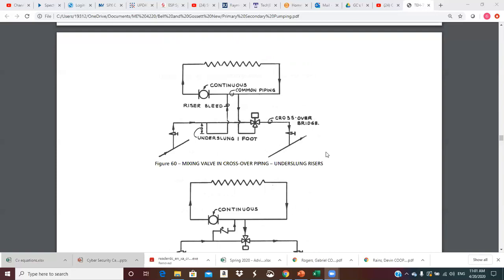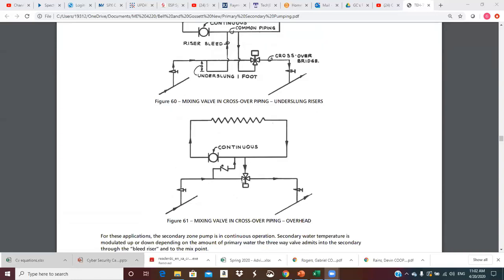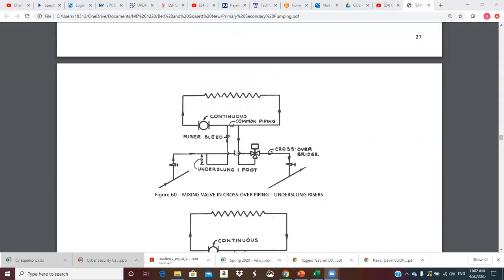Another benefit is that the particular location of the three-way valve requires an underslung bleed riser if the valve operator is placed at the top of the valve, which is common. The return port has to point downward, requiring this underslung return bleed riser. The underslung bleed riser provides a thermal anti-gravity flow lag, which eliminates the need for a flow control valve. The pressure at the secondary circuit pump can never be less than the primary circuit pressure as developed in the crossover bridge. The crossover bridge can also be balanced by proper selection — the proper CV rating on the three-way valve.